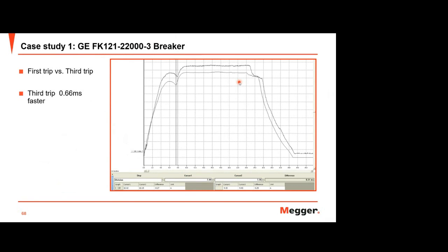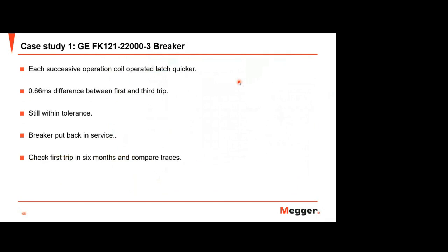But maybe in some conditions the deviation is no longer present. Still, if you compare first, second and third, normally you can see some difference for a breaker that never operated for a year, 2 years, or maybe more than 3 years. So it is still within tolerance and your breaker can be put back in service, but check the first trip and compare the trace. So at least they have data to compare on the next testing. Because they can prove on this, first trip testing gives you more real timing information compared to the conventional, or in some cases maybe the delay or difference between both will be higher.